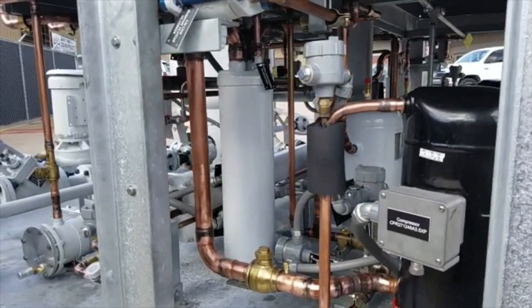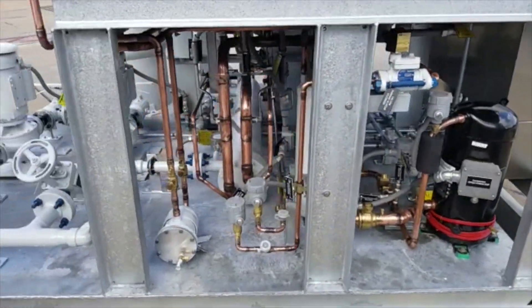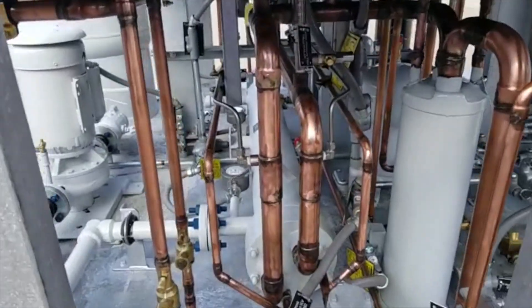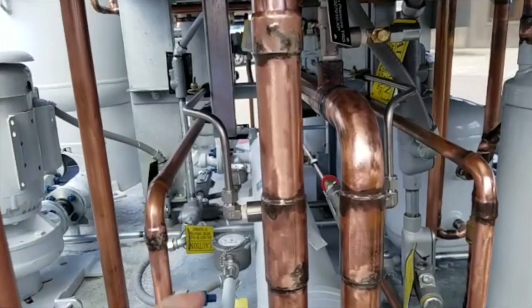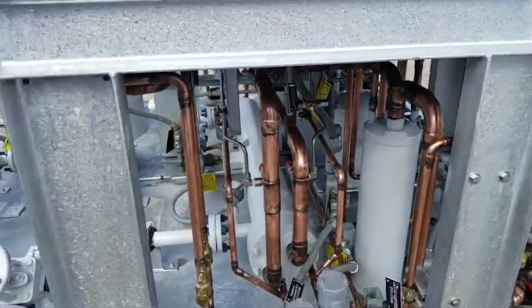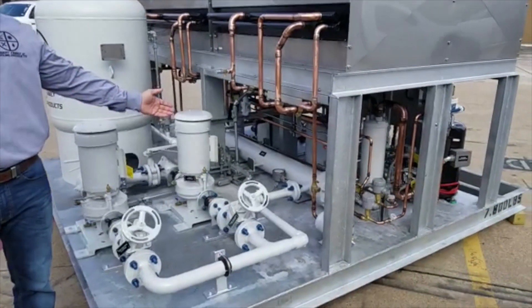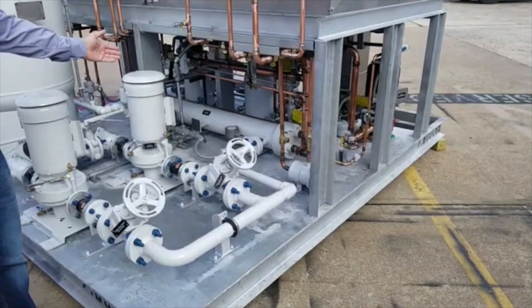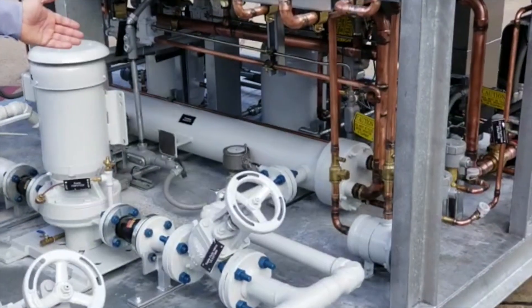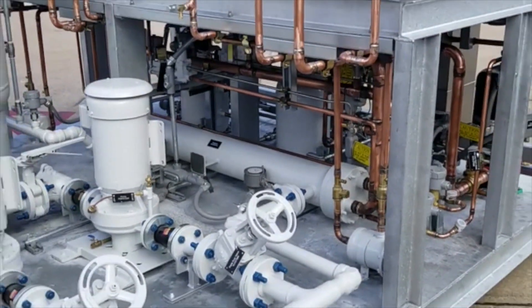It also has hot gas bypass. As you can see on the hot gas bypass, the sensing tubing is actually thick-wall stainless steel with a lot of fittings. What's unusual on the package is that we have a shell and tube evaporator. Most suppliers today would use a brazed plate, but here we go the extra mile to provide an industrial DX shell and tube evaporator.